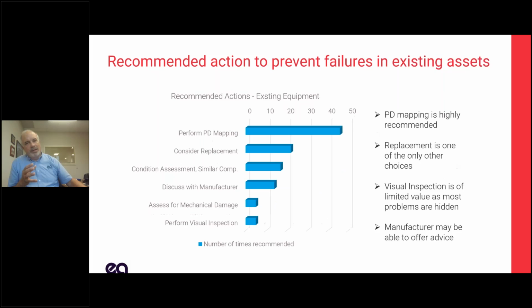Problem is, we've got a lot of existing equipment out there, and we've got limited things we can do. Partial discharge mapping and partial discharge testing of the cables is really good. You can replace cables ahead of time, maybe as a result of finding PD. You can discuss with the manufacturer: I'm getting these failures, what can I do about it? Visual inspection is pretty limited because you can't see most of the cables. So what are we going to do?